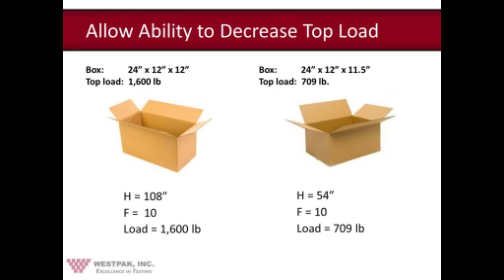So as Kevin discussed, one of the package validation inputs is the compression test. In this example, the target load is based on several factors, including the dimension of a shipper. If you're going to be testing to ASTM D4169, the compression formula will change based on whether your shipper is under or over 2 cubic feet. In the example that you see here, we have 2 shippers. The one on the left is 2 cubic feet, while the one on the right is slightly under 2 cubic feet, just based on that ½ inch dimension less. This difference of a ½ inch has an impact on the compression top load of close to 900 pounds, which is very significant.